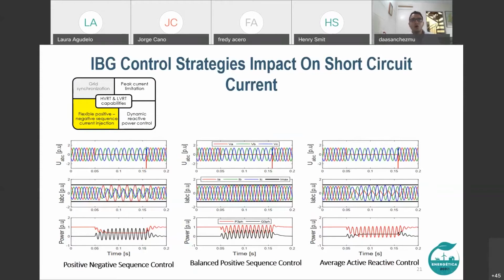Also, we can see the impact on instantaneous active and reactive power injection. Here we can see the active power oscillations are cancelled. Here we can see there are active and reactive power oscillations, and here we can see how the reactive power oscillations are cancelled. Also, in the first and the third, there is negative sequence current injection. But in the second, balanced positive sequence control, there is a suppression of negative sequence current injection. So there are many control strategies, and we have to evaluate the impact on short circuit current and on protection scheme operations.